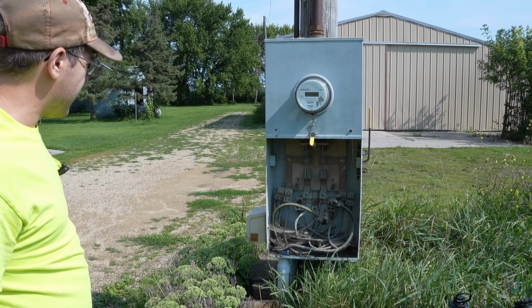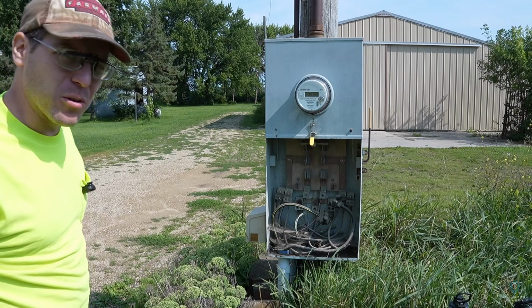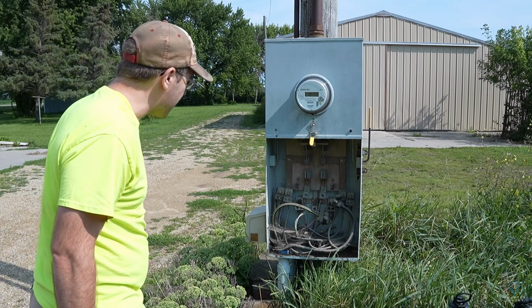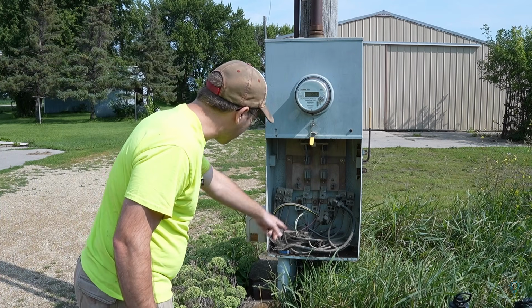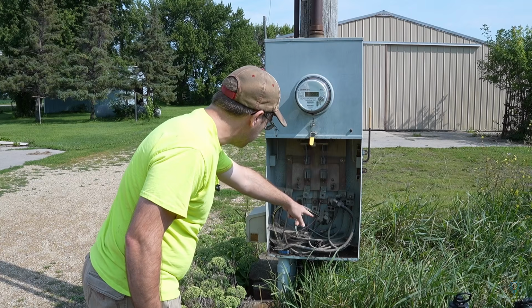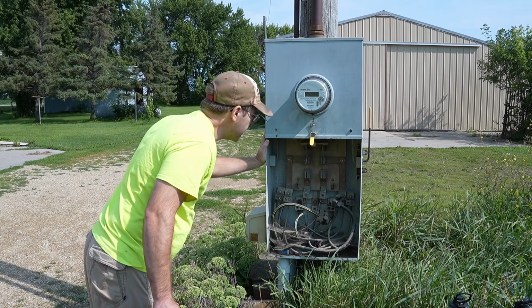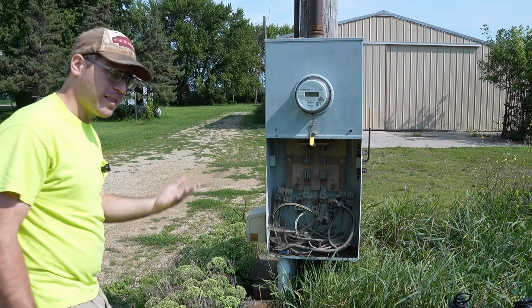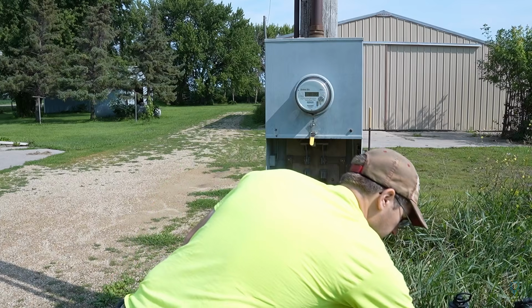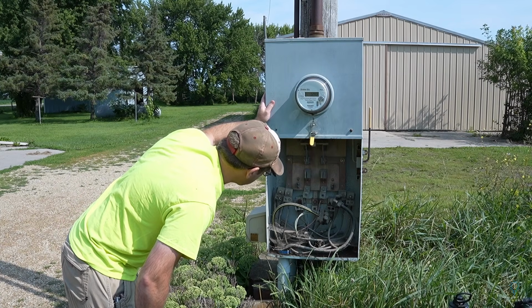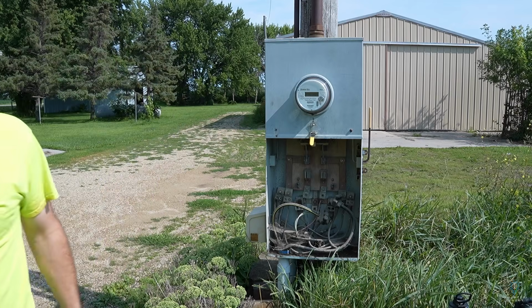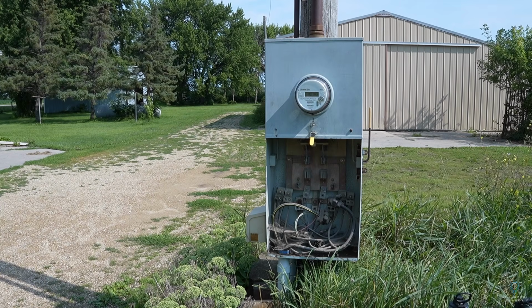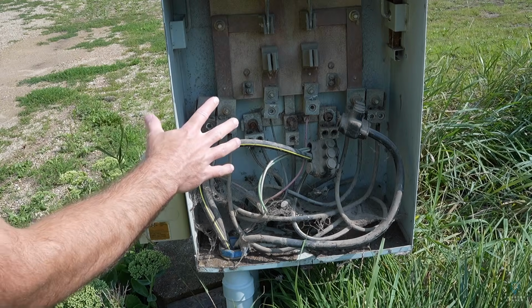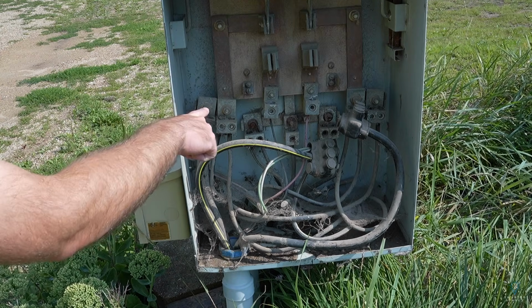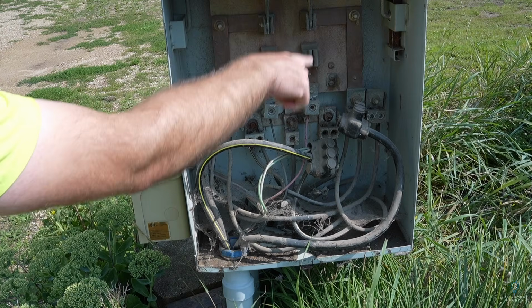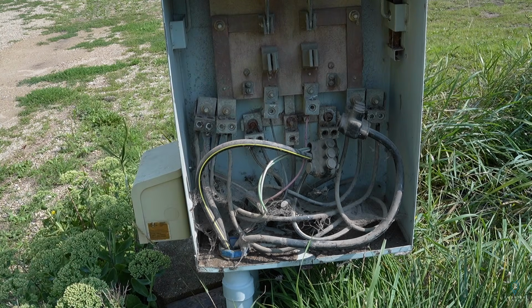Wow, that's a mess. I'm guessing we've got a corrosion issue, is my guess. Or who knows what they've got going on here with these Polaris connectors either. I really haven't been in here since we bought the property quite a few years ago. Holy cow, that's a mess in there. Look at all that corrosion. No wonder we've got voltage drop issues. This is a pretty sketchy distribution panel. Those are live exposed bus bars right there. So this is pretty sketchy working in here.